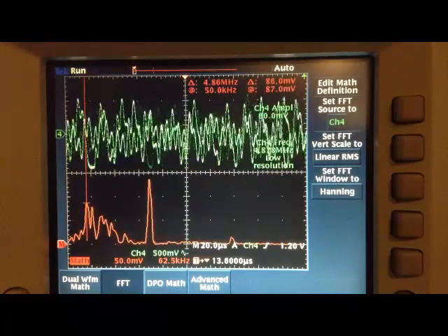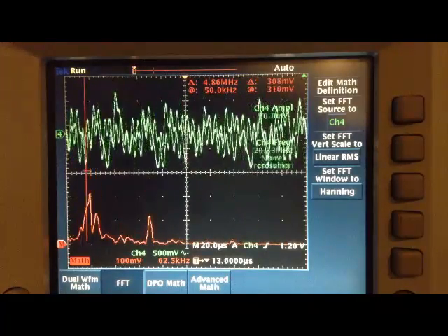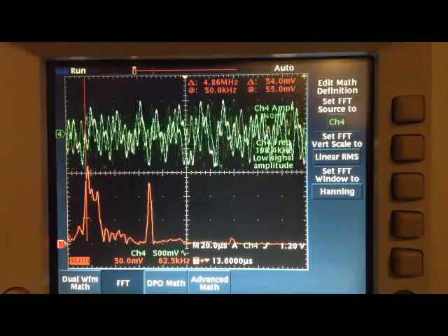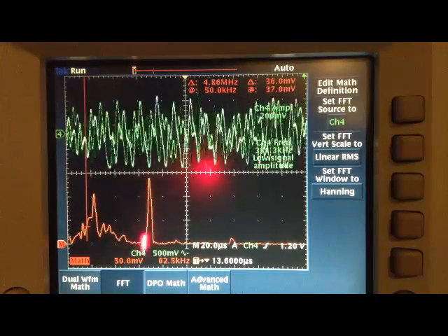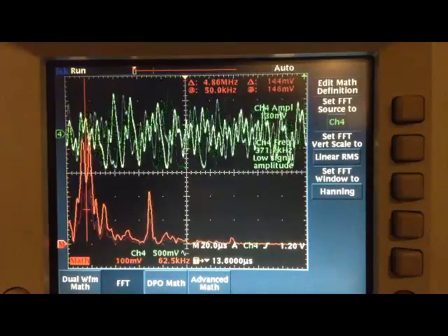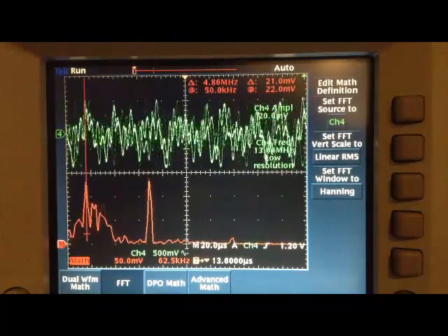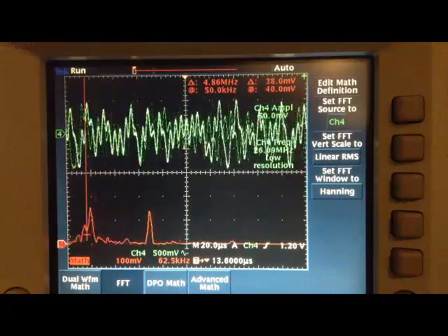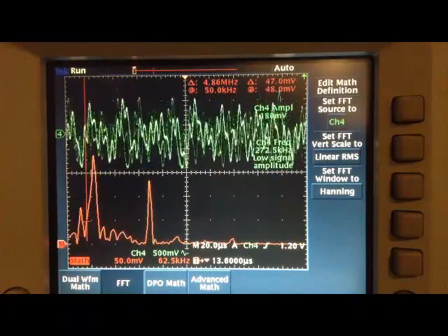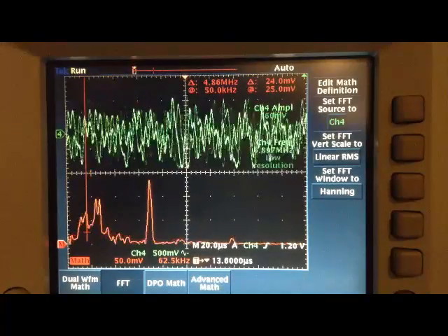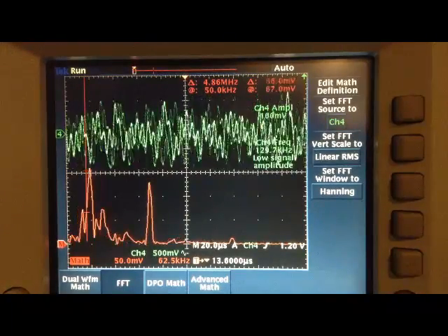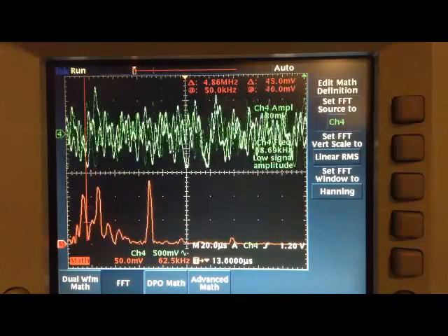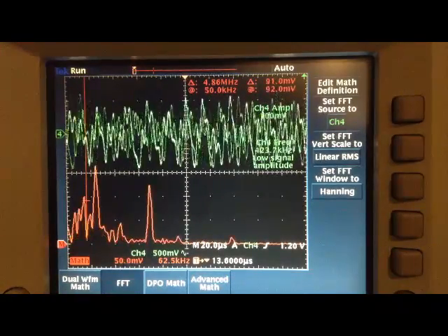It's one or more oscillations at around 50 kilohertz, and the second one up here is the remnants of the switching power supply, the high voltage power supply, and that frequency is stable. It's known to be 200 kilohertz. These signals combine at the front end of the preamplifier, and so they both affect the output.